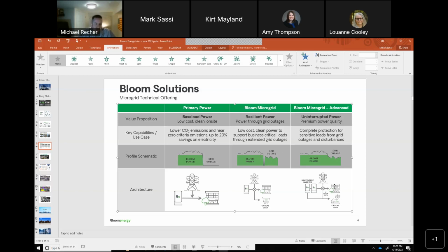A more advanced version of that microgrid offering is a scenario where all the loads are on the fuel cell all the time, and the utility is there as a backup. If there's ever an outage, there's no transition of equipment swinging over—no automatic transfer switch or breakers need to transition, as the loads won't see an outage during the utility outage. This allows those loads to continue operating as long as the fuel cell is on-site and operating. So those are three examples of the base fuel cell offerings that Bloom provides as a platform for power generation on site.